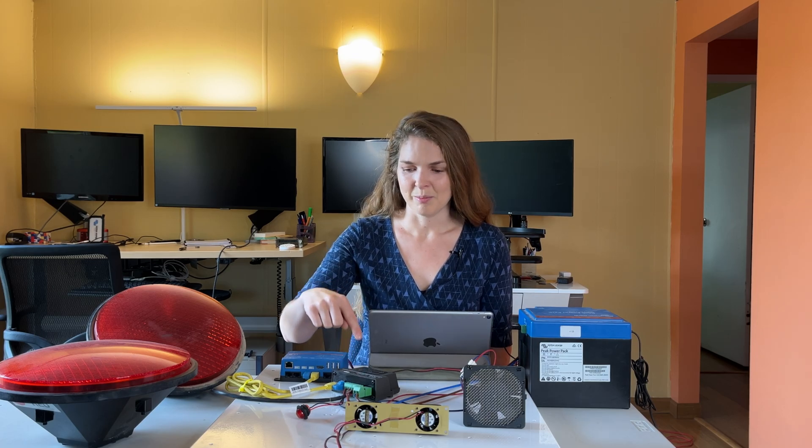Again, each output is fused up to five amps. And if that isn't enough capacity for you, you can piggyback or use the smart switch as a helper relay with an additional 12 or 24 or 48 or 120 volt relay. Of course, when we do that, we lose track of the current flow to the load, but we're still able to see that the relay is operating.